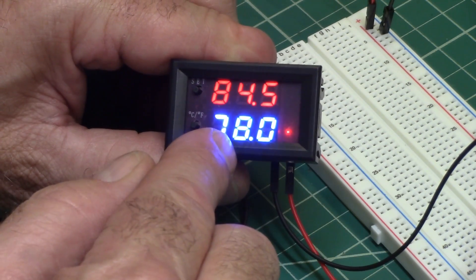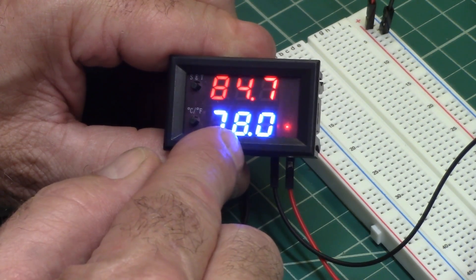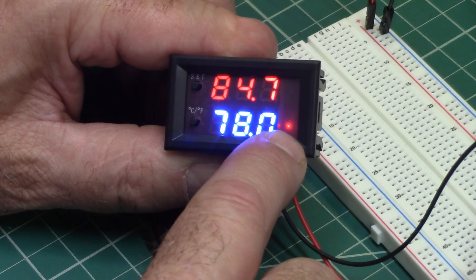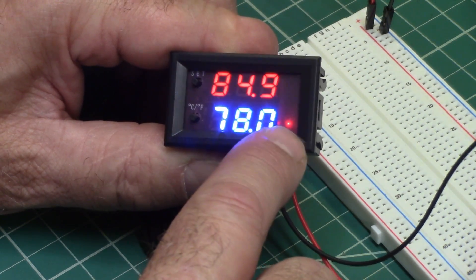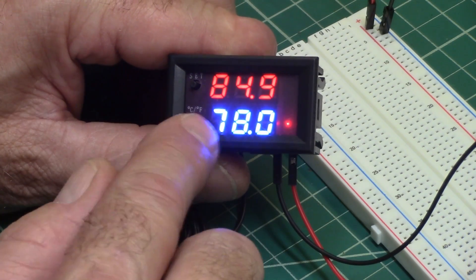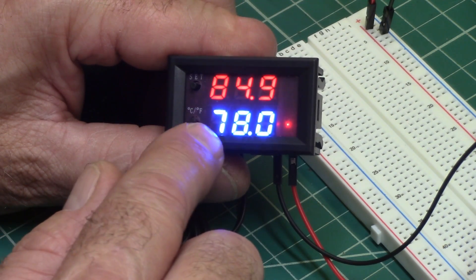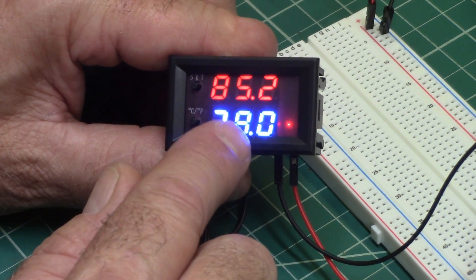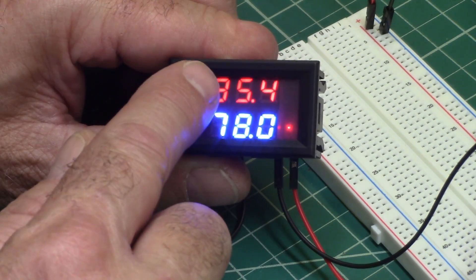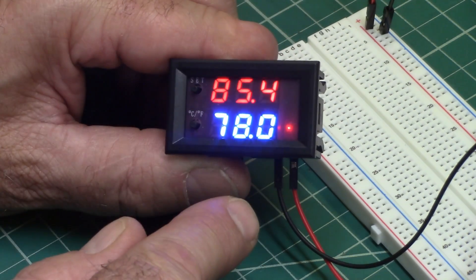So let's say you set this to 78, and you want it to cool. This one is set up for cooling right now. So it's 84 degrees in here. You can see the little red light, which means that it's active. So if you had this hooked to something like a fan, it would be running that fan right now. And so if you want it to go to 78, and then come on when it gets to 80, in other words, it'll cool it down to 78, and then it'll warm slowly, and then when it hits 80 degrees, it'll come back on.